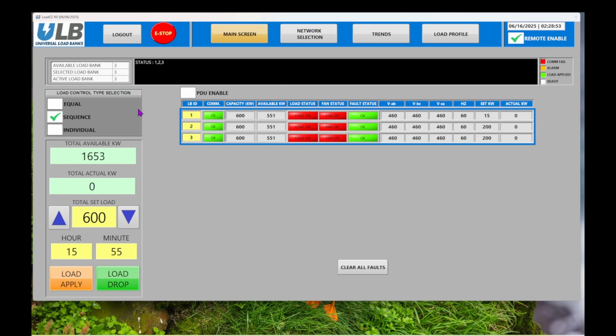You can choose between three control modes. Equal evenly distributes load across selected load banks. Sequence applies load in a step-by-step sequence. Individual lets you manually set kilowatt values for each load bank.